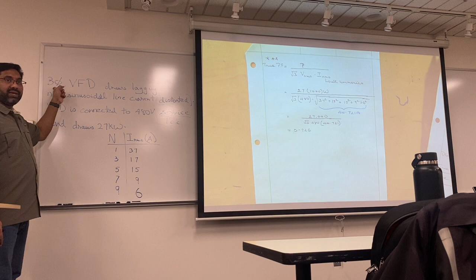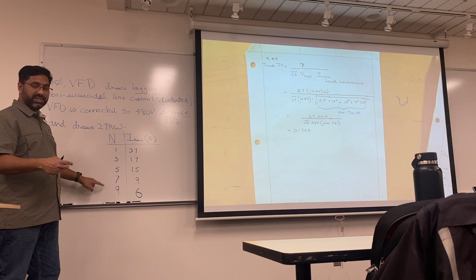Keep in mind this is three-phase. If I give you a two-phase system, don't jump to 3 and 9, you have to look for the even numbers instead, and I'd give you all those numbers. We derived that for the neutral, only the triplen harmonics matter. But when sizing wire gauge for your lines, you have to consider all the currents.